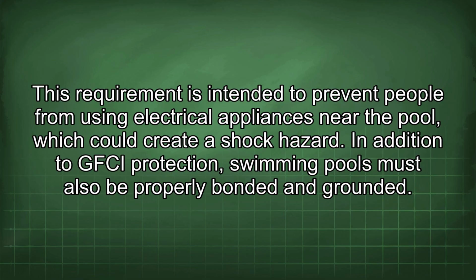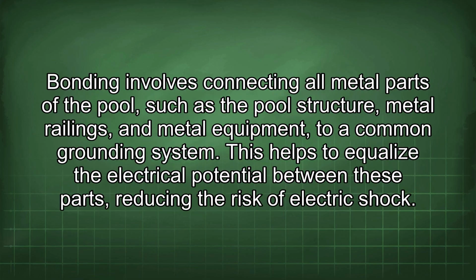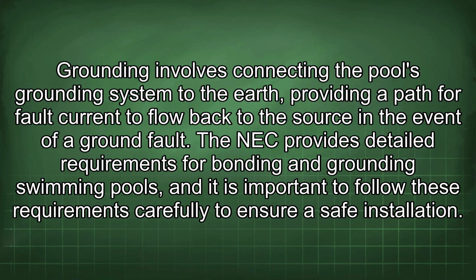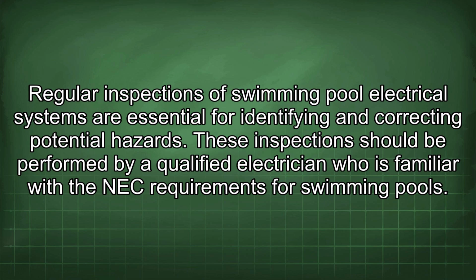In addition to GFCI protection, swimming pools must also be properly bonded and grounded. Bonding involves connecting all metal parts of the pool, such as the pool structure, metal railings, and metal equipment, to a common grounding system. This helps to equalize the electrical potential between these parts, reducing the risk of electric shock. Grounding involves connecting the pool's grounding system to the earth, providing a path for fault current to flow back to the source in the event of a ground fault. The NEC provides detailed requirements for bonding and grounding swimming pools, and it is important to follow these requirements carefully to ensure a safe installation. Regular inspections of swimming pool electrical systems are essential for identifying and correcting potential hazards.